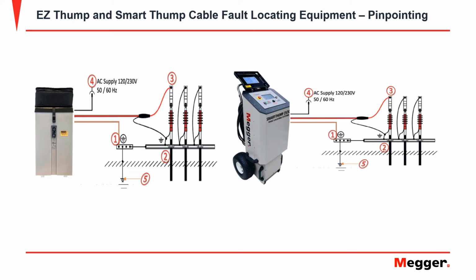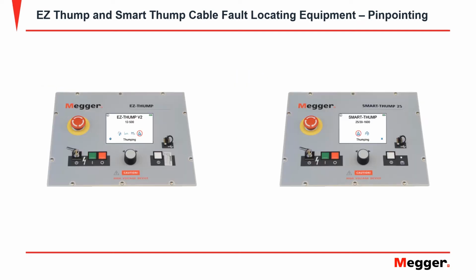For a brief connection overview, first, apply your equipment safety ground to ground. Then apply your high voltage return lead to the concentric neutral or shield under test. Finally, place your high voltage output lead to the cable under test. Thumping is a pinpointing technique which is used by having an arc flash at the fault point.